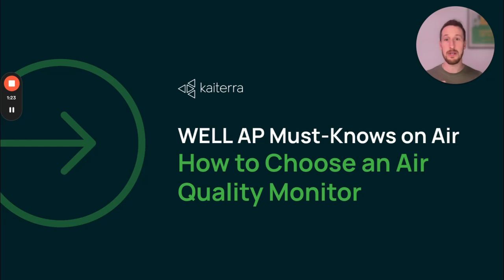And that means that you need to choose a monitor that measures PM2.5, PM10, TVOC, CO, and O3. So that's carbon monoxide and ozone, those last two. And if you really want to get maximum return for the investment on sensors, you also want that monitor to measure CO2, carbon dioxide, as well as NO2.